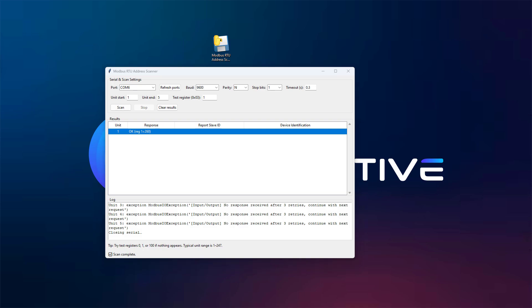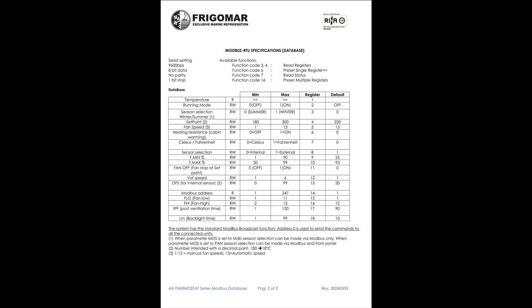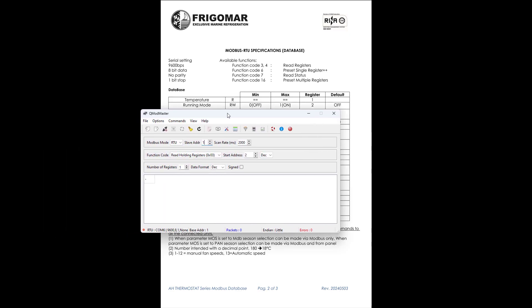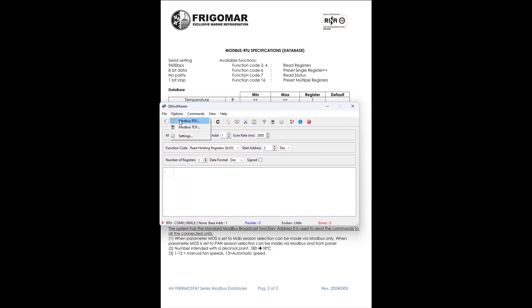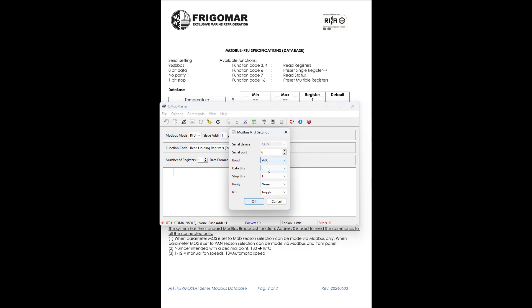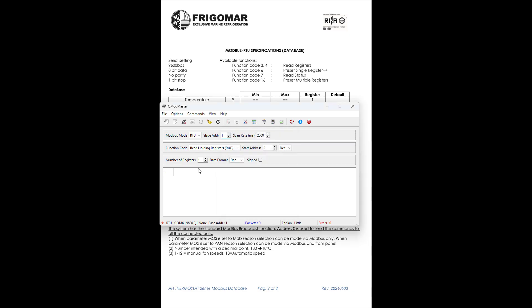This tells us that the device we connected is responding on slave address 1. With that information confirmed, we can now move on to the next tool, QModmaster, which is available online for download. You'll also find the link in the description. Inside QModmaster, the first step is to open the options menu and select Modbus RTU. Here we configure all the serial parameters so that they match the values specified in the device documentation. Once that's set, we can click the Connect icon. If the COM port and serial settings are correct, the connection will succeed, and the green indicator in the lower left corner will confirm it.